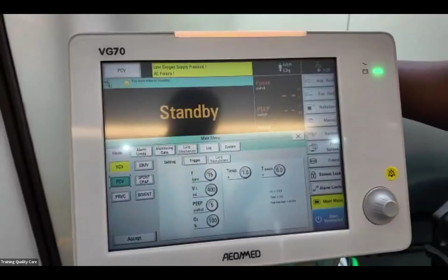But I've not seen a literature that talks about anything less than 4. So let's keep it at the physiologic level. Then since we are cycling volume, we want to set the tidal volume. And the tidal volume for a normal lung is 6 to 8 mils per kg. So for our ideal body weight was 53. So I can choose 6 or 8. See, if the chest is okay, you can choose 8. So 8 mils times 53. 8 times 53.